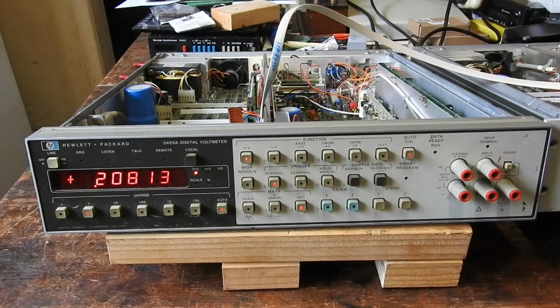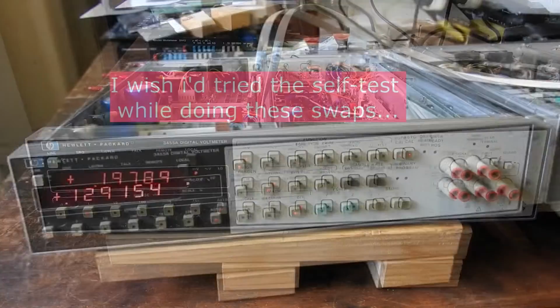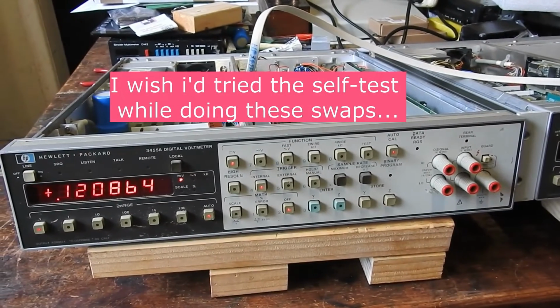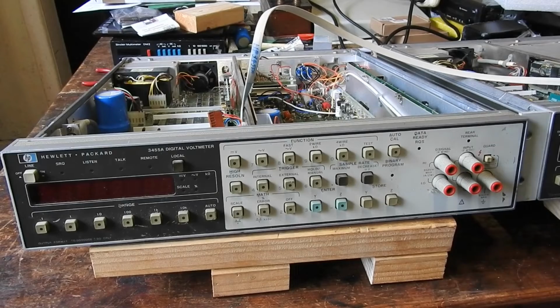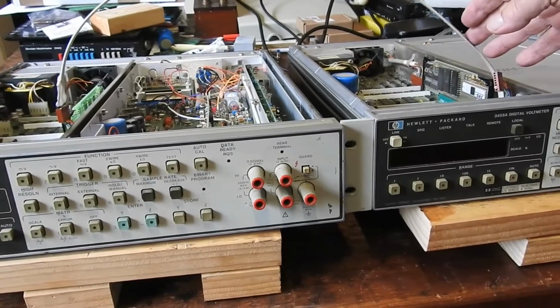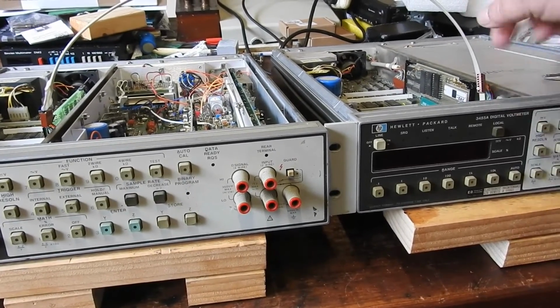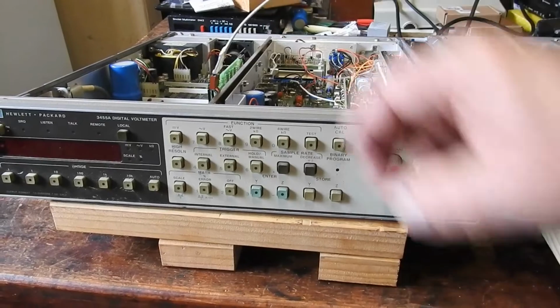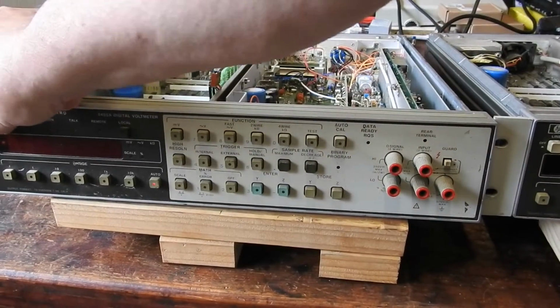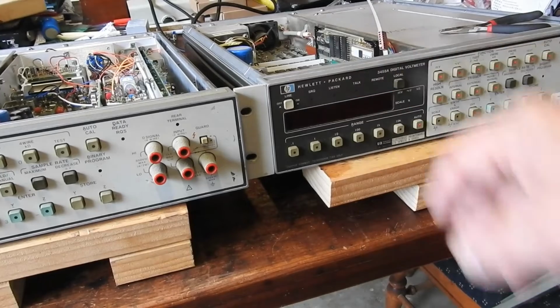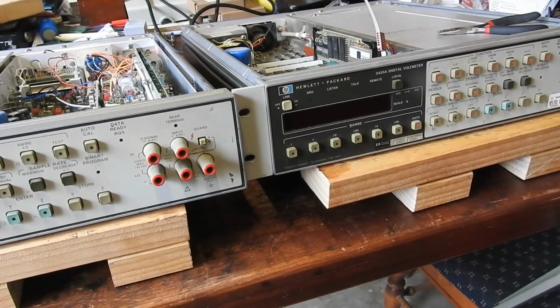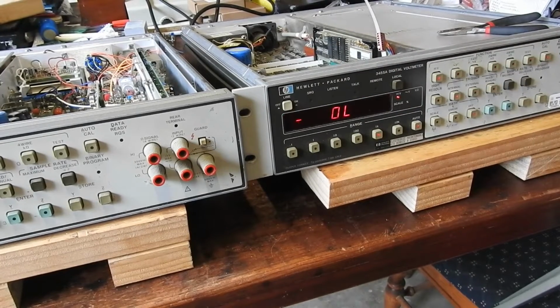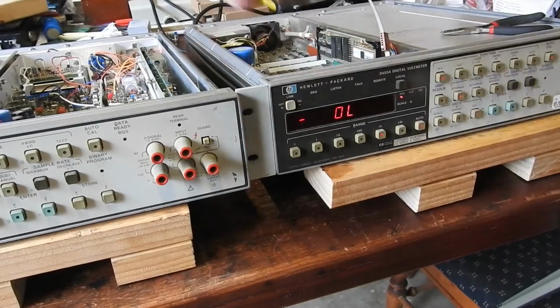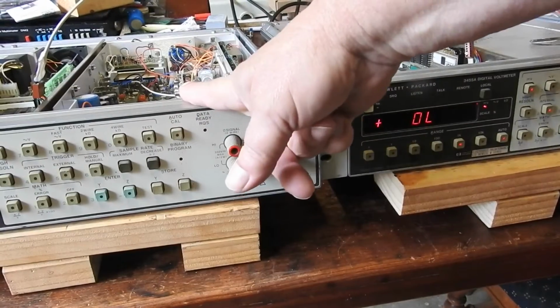So this one's now working. So the problem is something in its in guard. Just to verify, I'll swap them over. Right, now I've got this going to the out guard on that one and to the in guard on this one. So now we turn this one on first, and this one should now do that OL, overload. So confirmed. Problem is in the in guard area.